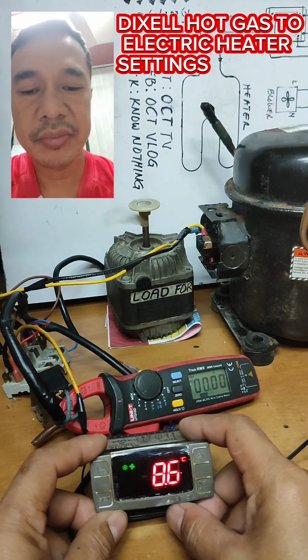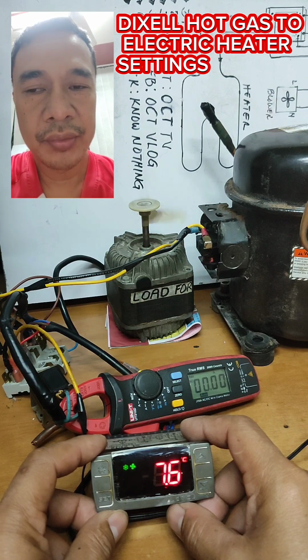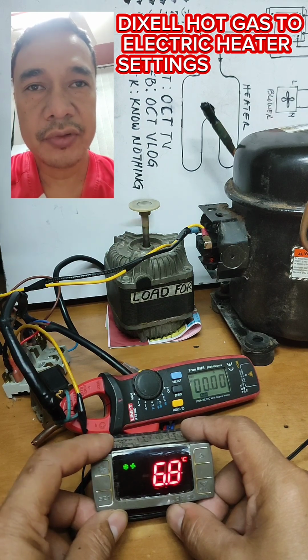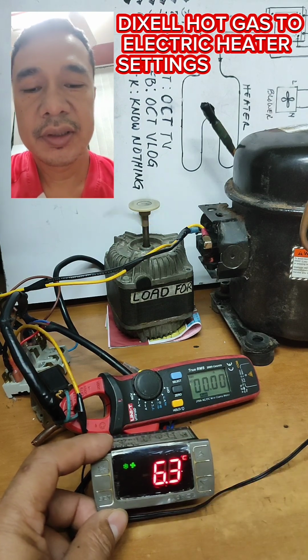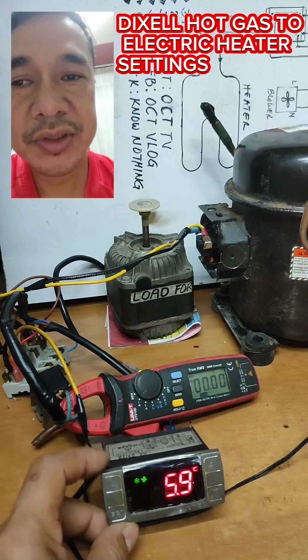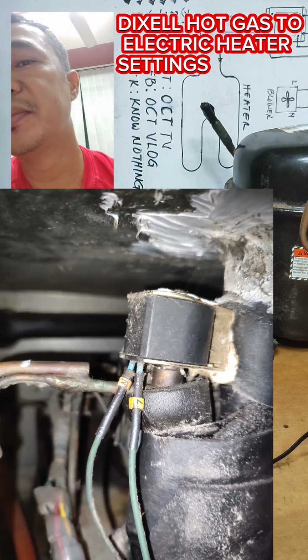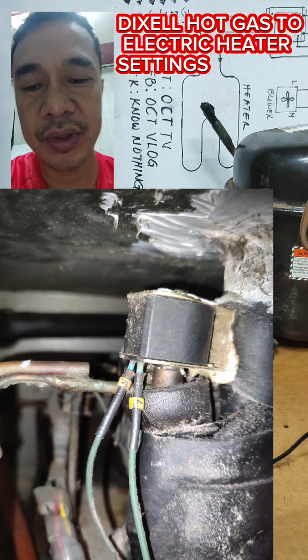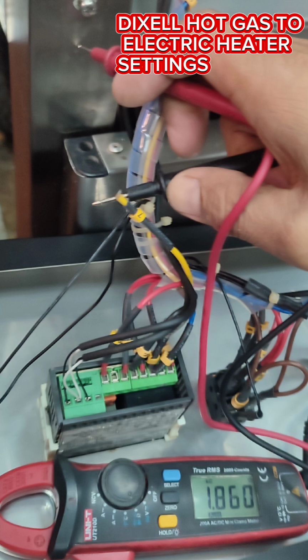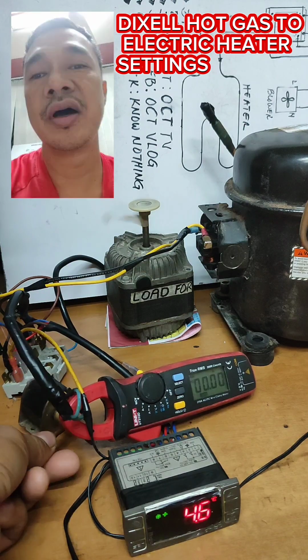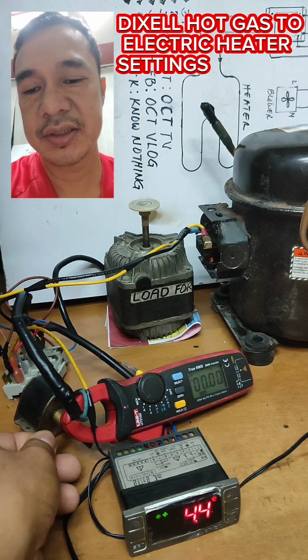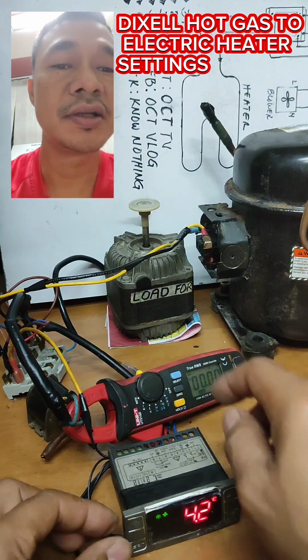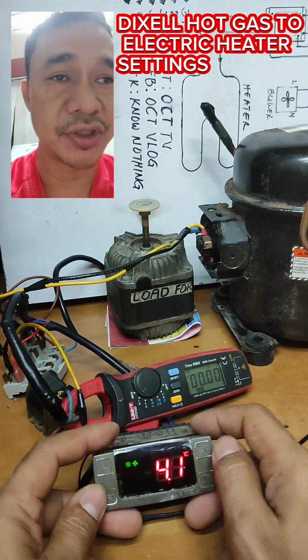Okay, it's a make table, and when a defrost happens, it trips because the solenoid valve is shorted. When I check it, it is shorted, and that solenoid valve looks like this. So that one is hot gas defrosting.